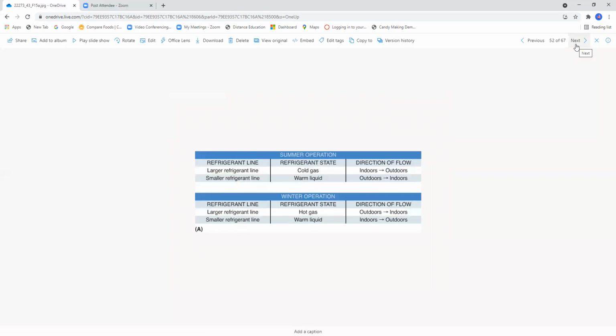Summer operation: the large refrigerant line is going to be cold gas. The small refrigerant line is going to be warm liquid, with direction of flow indoors to out, and outdoors to in. In the winter operation, it's just the opposite. The large refrigerant line now becomes hot gas. The small refrigerant line becomes warm liquid, with direction of flow outdoors to indoors, and indoors to outdoors.